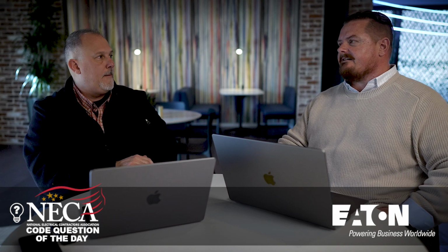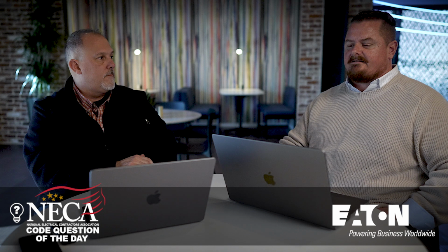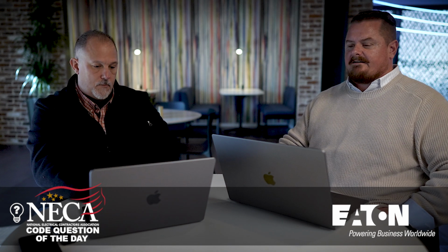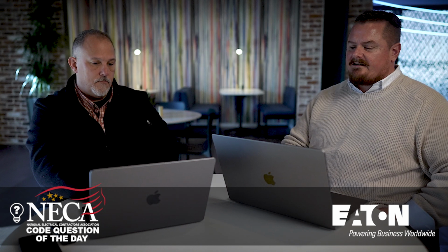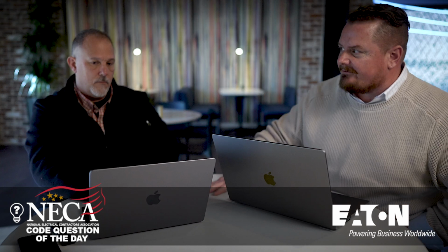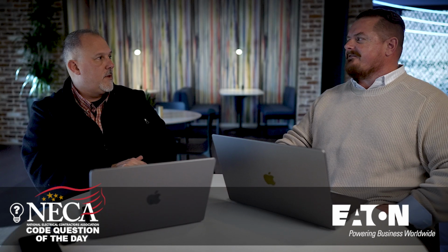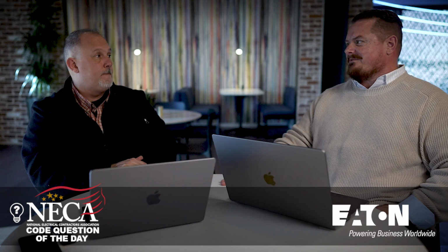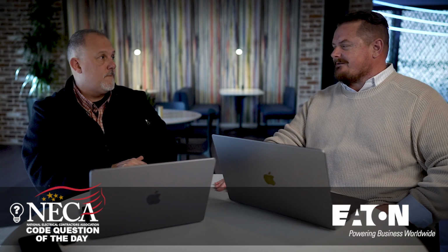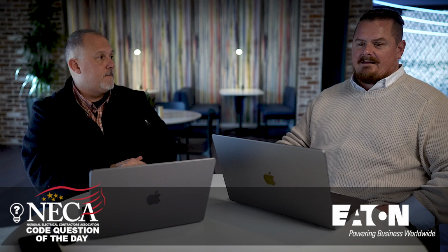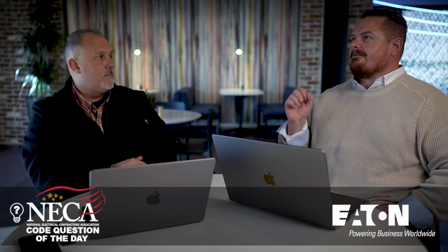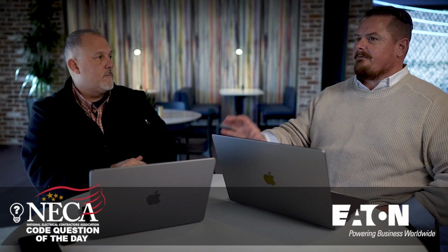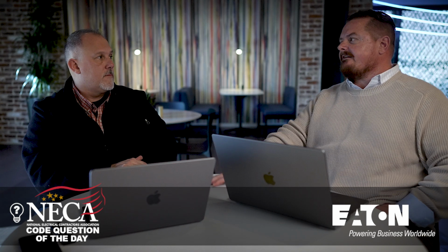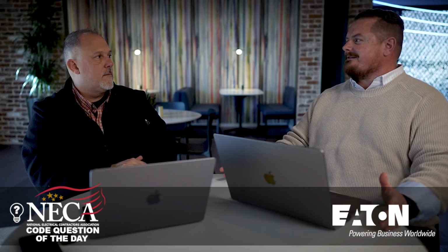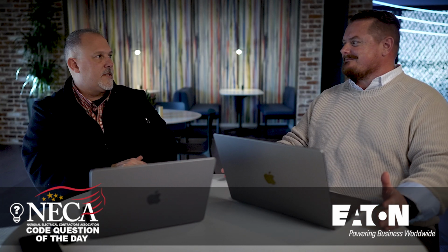It's something that is industry wide and is one of those things that continually is an issue, and until we get it figured out. But you touched on another thing in your discussion, and that's incident energy. The safety element that available fault current plays in the world of electrical equipment, right? And it just proves even further into that point. We've got all these requirements from an electrical safety standpoint. We've got NEC requirements that say the equipment's got to be rated properly. There really is no excuse anymore that this information is not available. Oh, that's exactly right. Yeah.